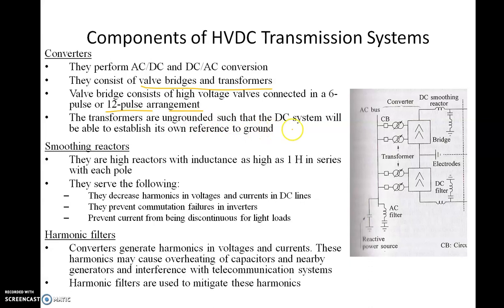Smoothing reactors are high-value reactors with very large inductance — it may be as large as 1 Henry in series with each pole, meaning each converter output. They decrease harmonics in voltages and currents in DC lines.